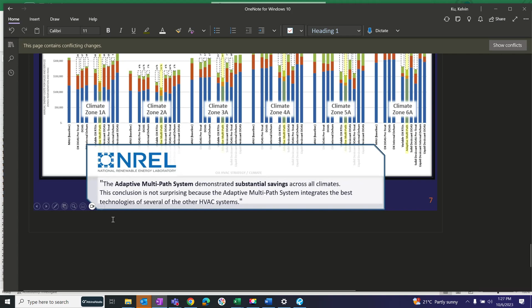One thing we see, unfortunately, quite a bit, especially in the South, is contractors seeing a store that feels too humid and screwing down the outside air dampers, thinking the outside air is the source of moisture - and it is. But if you shut down the machine bringing it in, where does the moisture come from? It comes through the walls, through the docks, through the front door. Now you have untreated humid air flooding into your store, going right to your refrigerated cases. That's the wrong approach.